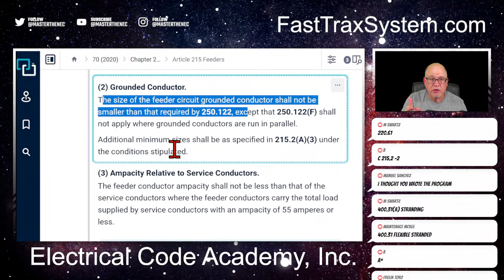Now, we're also talking about what? The equipment grounding conductor is sized per 250.122, right? But this is also reminding us that, hey, by the way, that grounded conductor can also not be smaller than what we require by 250.122. Okay, now, is it going to be larger? Yeah, probably is, based on a load calculation and what the neutral load is. But we already know it can't be smaller than what's required by 250.122. Okay?